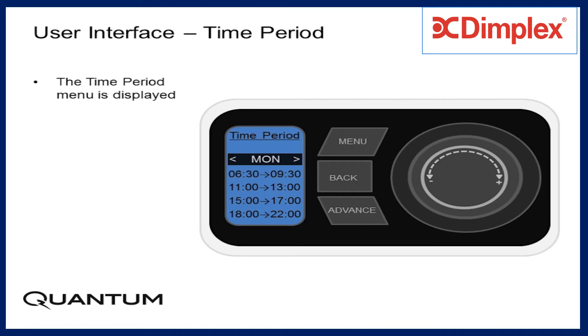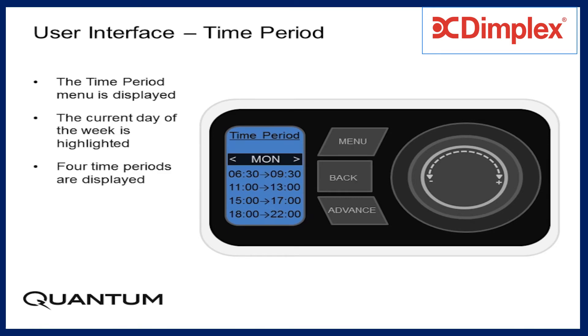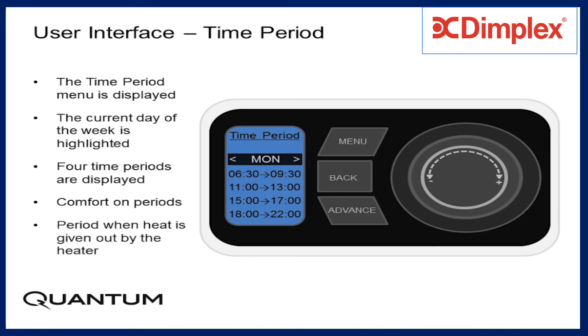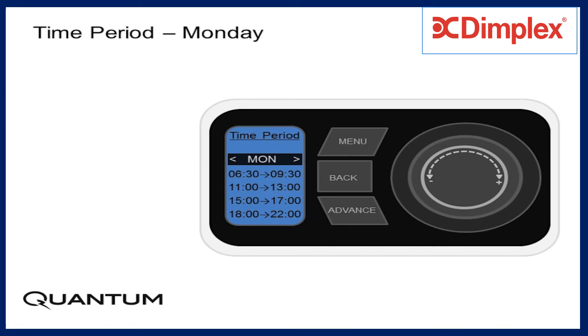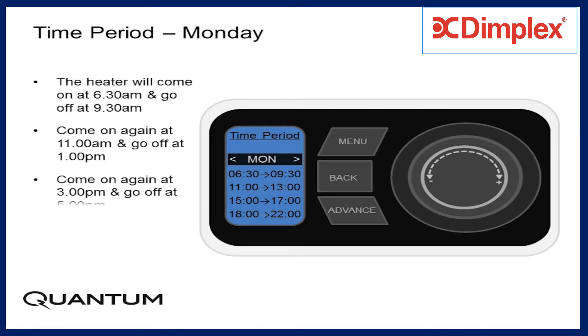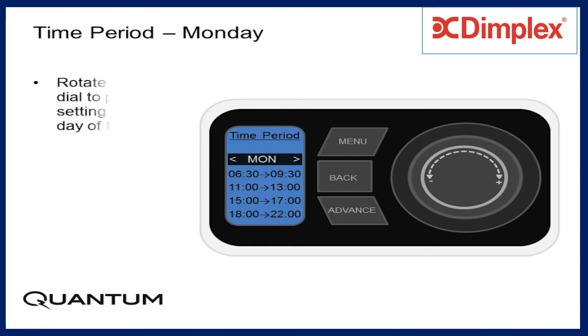The time period menu is displayed. The current day of the week is highlighted and four time periods are displayed — these are the comfort-on periods, the periods when heat is given out by the heater. The heater will come on at 6:30am and go off at 9:30am, come on again at 11am and go off at 1pm, come on again at 3pm and go off at 5pm, and then come on once again at 6pm and go off at 10pm.